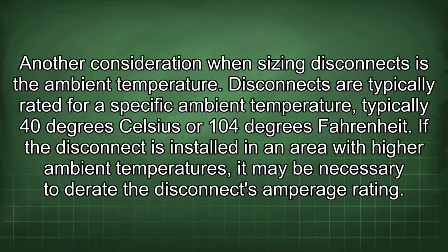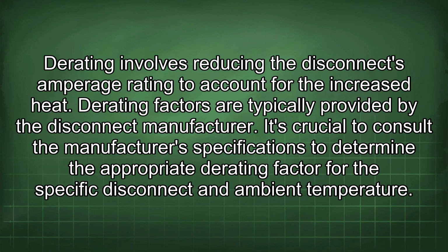Another consideration when sizing disconnects is the ambient temperature. Disconnects are typically rated for a specific ambient temperature, typically 40 degrees Celsius or 104 degrees Fahrenheit. If the disconnect is installed in an area with higher ambient temperatures, it may be necessary to derate the disconnect's amperage rating. Derating involves reducing the disconnect's amperage rating to account for the increased heat. Derating factors are typically provided by the disconnect manufacturer. It's crucial to consult the manufacturer's specifications to determine the appropriate derating factor for the specific disconnect and ambient temperature.